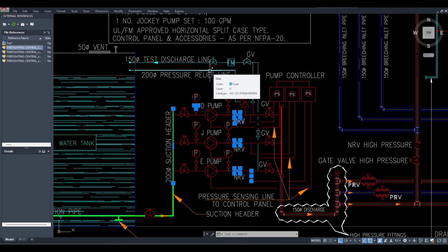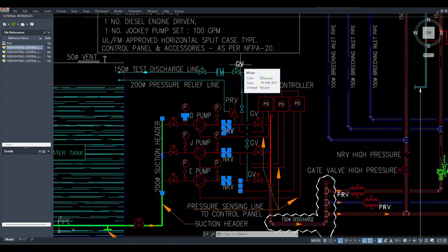So in FM, what you will check is whether these pumps are connected with the test line or not. Then whether in the test line a flow meter is there or not. And if the flow meter is there, whether the isolation valves are given back and forth or not. That way you can check whether this system is correct or not. If anything is missing, then it's missing, so you need to check.